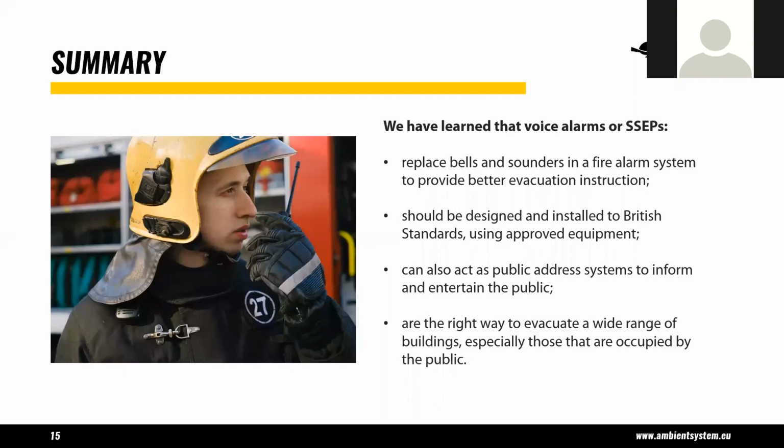So in summary, we have learned that voice alarm systems replace bells and sounders because people then respond. They should be designed, installed, and maintained to the British standard BS 5839 Part 8 Code of Practice, and you should use the approved equipment with the EN54 certification, which is mentioned in those documents.